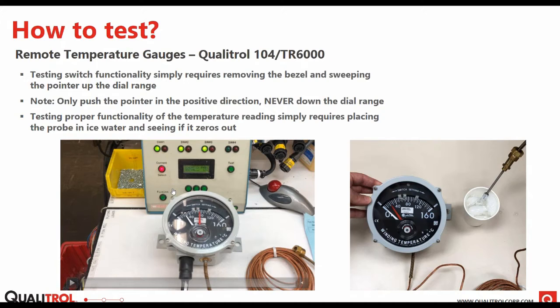So remote temperature gauges are used for, obviously, oil temperature and winding temperature, top oil and winding temperature. And these can also be used for alarms or cooling stages, turning on your cooling fans, pumps, your whole cooling system. So you really want those switches to be working and know that they're working. So, testing our remote temperature gauge.